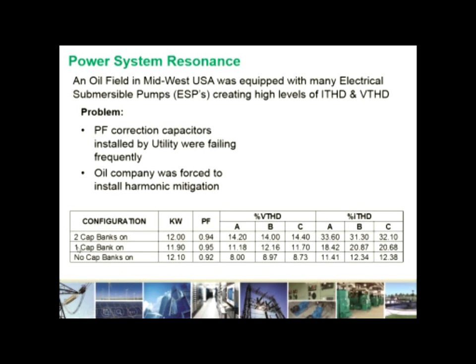So when they took one capacitor bank off, you can actually see the power factor actually increased slightly rather than dropping. And this was the result of the voltage distortion dropping as well, because we essentially were removing part of the resonance in that system.